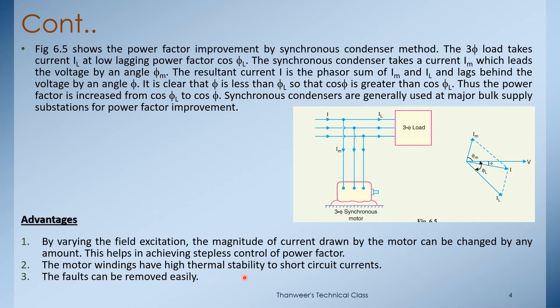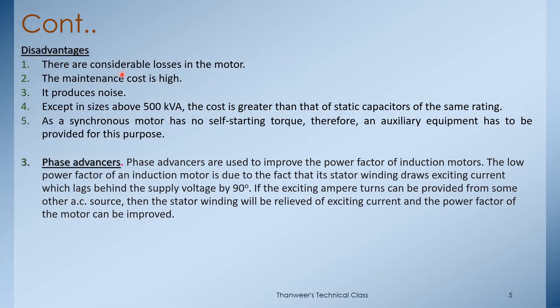Advantages: motor windings have high thermal stability to short circuit current, and faults can be removed easily. Disadvantages: there are considerable losses in the motor, maintenance cost is high, and there is noise. For sizes above 500 kVA the cost is greater than that of a static capacitor. Also, a synchronous motor has no self-starting torque and requires auxiliary equipment.